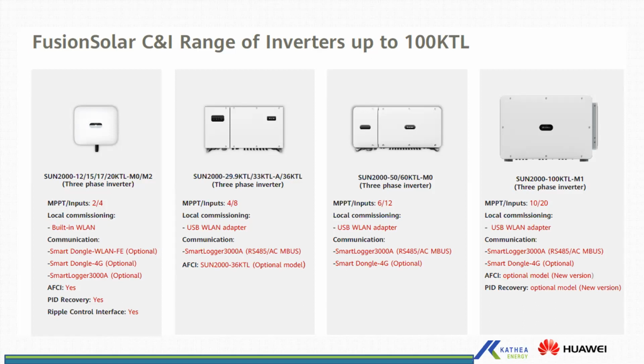HUAWEI inverters, due to a rise in concern in arc faults, I'm sure if you are following PV in the commercial, industrial, and utility, it's been a major concern. Having arc faults, these are high voltage systems, so they can easily cause fire. One major incident that happened was at Walmart warehouses. I think about 3 of them were ablaze with fire due to arc fault. So our inverters have built-in arc fault detection, so they can actually detect an arc fault on PV strings that is positive to ground, negative to ground, or positive to negative, and shut down the inverter wherever necessary.